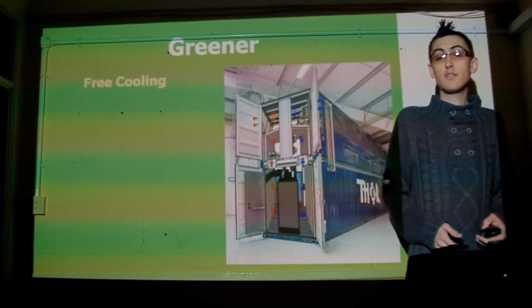So how does the Thor data centre exploit Iceland's unique ecosystem to make it more environmentally friendly? Free cooling is a technique that inducts the cold outside air into a closed air circulation chamber above the warm server space which it cools. This system can be applied to a now common racked ISO container or to room layouts.